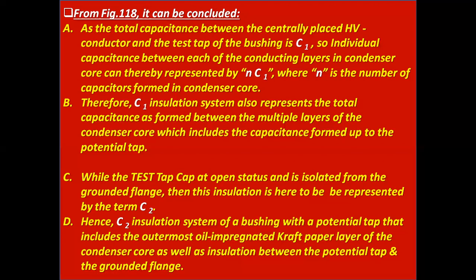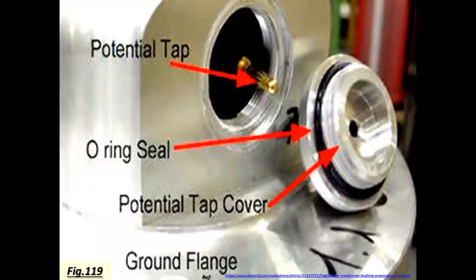While the test tap cap is open and isolated from the grounded flange, this insulation is represented by the term C2. Hence, the C2 insulation system of a bushing with a potential tap includes the outermost oil impregnated kraft paper layer of the condenser core, as well as the insulation between the potential tap and the grounded flange. See the diagram of the potential tap with tap cover and ground flange.